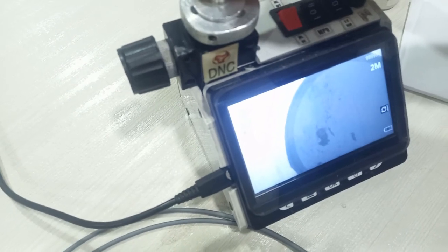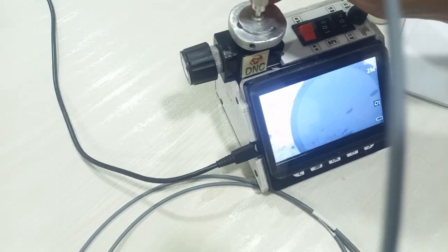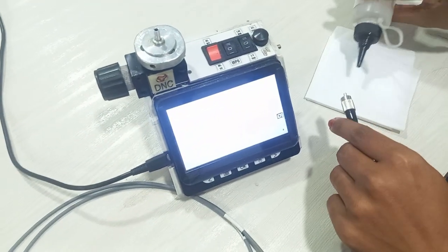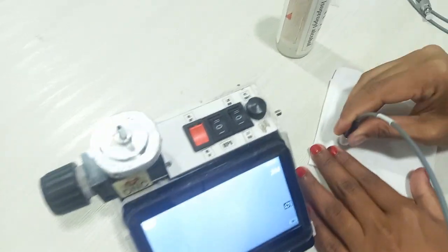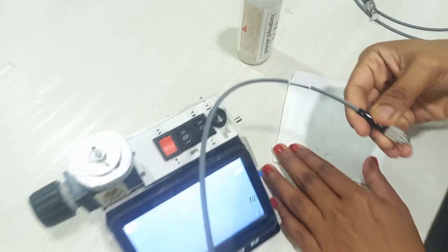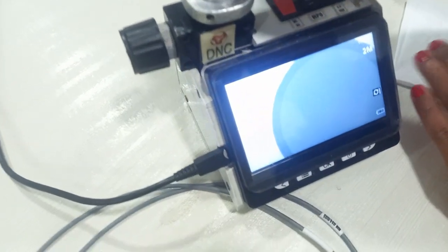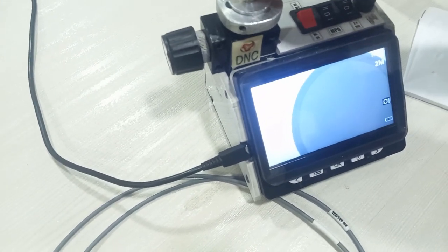The dark spots indicate the dust particles present at the tip of the fiber. This causes loss. So in order to clean, we use an IPA solution and wipe it. It will clean the dust particles. Now the end face is perfect and clean.